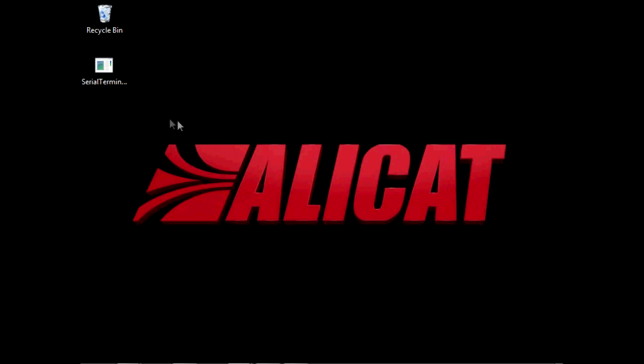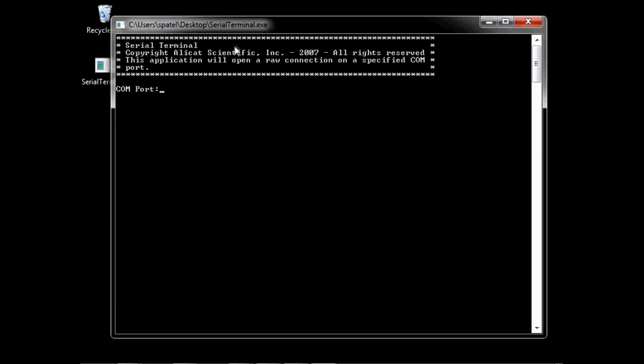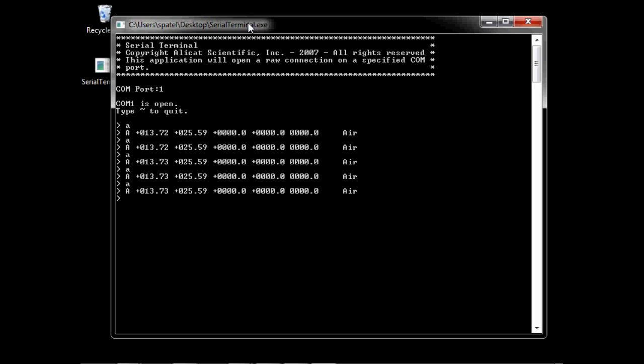With the Serial Terminal program unzipped to the location of your choice, execute the file and note first that the program will ask you for the COM port number that is being used by this connection. Type in this number, followed by the Enter key. In our example, the COM port is number 1. Because we have already confirmed our unit identifier as being the letter A for this unit, simply type the letter A, followed by the Enter key. You can now repeat these keystrokes and receive a line of data each time A Enter is typed.